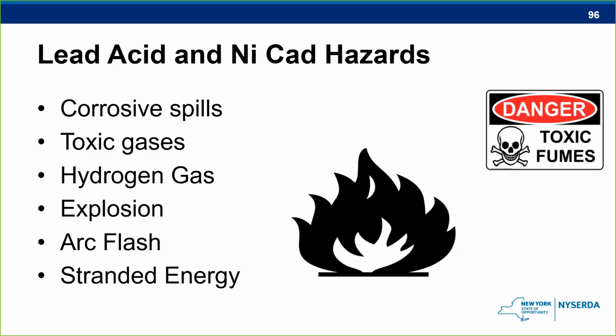Sometimes when they do overcharge, they'll put out a little bit of a toxic gas, but the big problem that happens is the hydrogen. But when there is a hydrogen release on these things, they have that little exhaust fan, and Jennifer alluded to that earlier, that this is part of the requirements of having lead acid and nickel cad inside the building. You've got to have those exhaust fans, and they have to be monitored for the hydrogen. So if it reaches 25% of its LFL inside the room itself, those fans will kick on and pull that stuff out. One of the things that the responders that are on here should be aware of is if you happen to get a call for an overcharged battery and you get a CO detector reading on your CO meter, that is a cross sensitivity with the hydrogen.